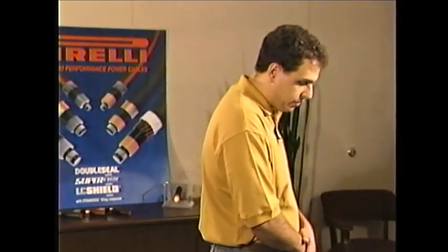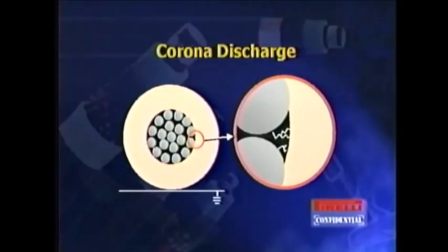When you get into medium voltage cable design, you have a whole new realm of problems to deal with. One of those problems is a phenomenon called corona discharge. Anytime you have a potential difference between a void anywhere in the insulating material, what you're going to do is draw an arc across that air gap. The air in that air gap will become ionized. And this causes degradation of the insulating material on either side. And over time, this will cause a cable failure.